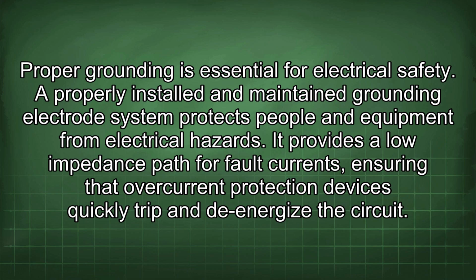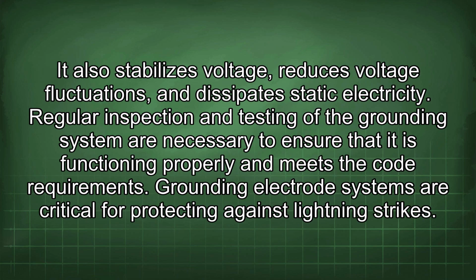A properly installed and maintained grounding electrode system protects people and equipment from electrical hazards. It provides a low impedance path for fault currents, ensuring that overcurrent protection devices quickly trip and de-energize the circuit. It also stabilizes voltage, reduces voltage fluctuations, and dissipates static electricity. Regular inspection and testing of the grounding system are necessary to ensure that it is functioning properly and meets the code requirements. Grounding electrode systems are critical for protecting against lightning strikes.